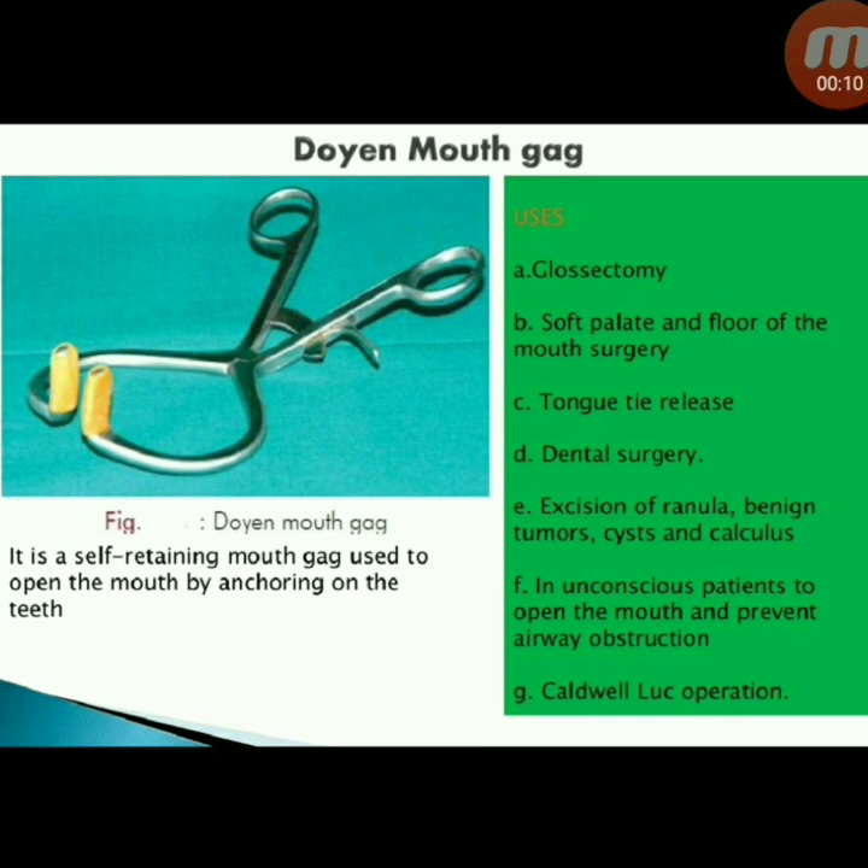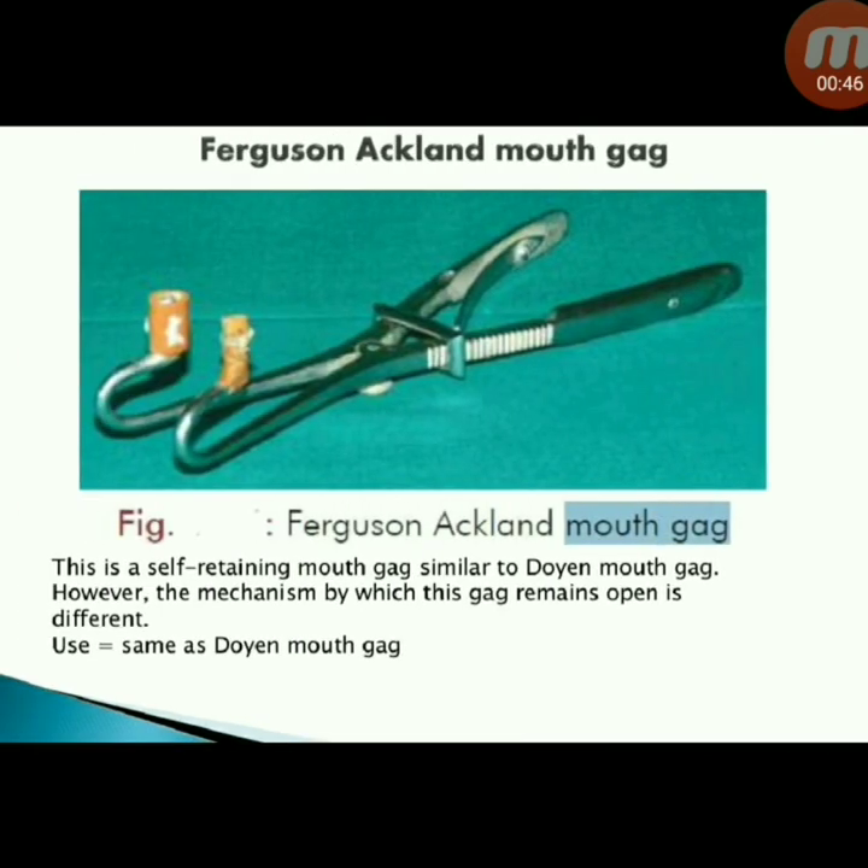Next instrument: Doyen mouth gag — a self-retaining mouth gag used to open the mouth by anchoring on the teeth. Used for glossectomy, soft palate and floor of mouth surgery, tongue tie release, dental surgery, excision of ranula, benign tumors, cysts, and calculi, in unconscious patients to open the mouth and prevent airway obstruction, and in Caldwell-Luc operation.